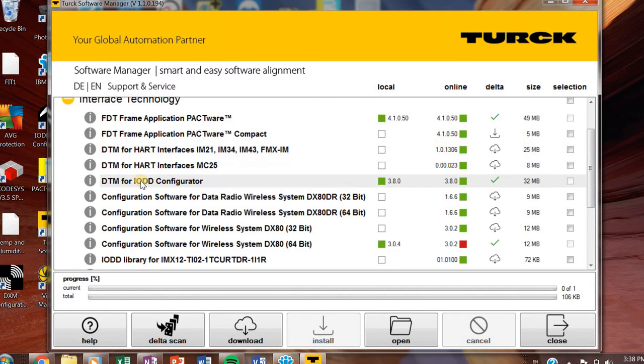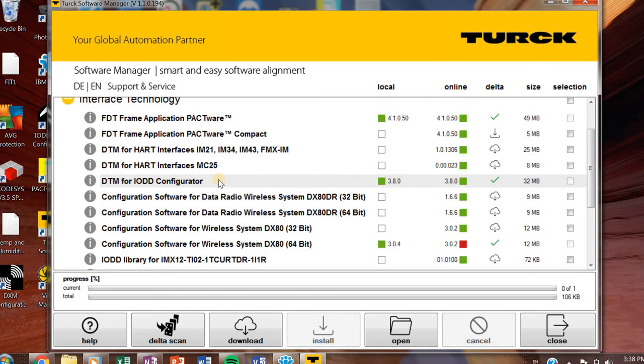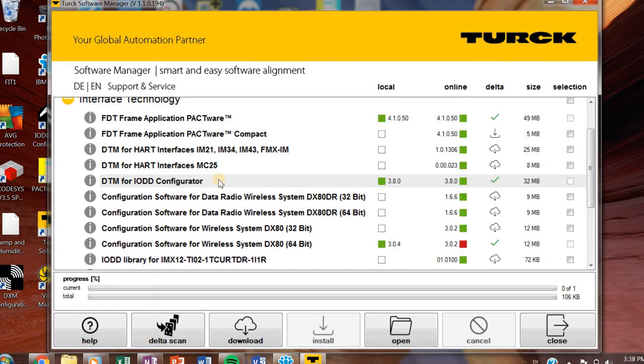DTM for IODD configurator. So when you're working with IO-Link, you need to convert IODD files into DTM files, which are then available to be imported into Pactware for configuration and seeing a bunch of cool stuff. So you'll need that if you're working with IO-Link.